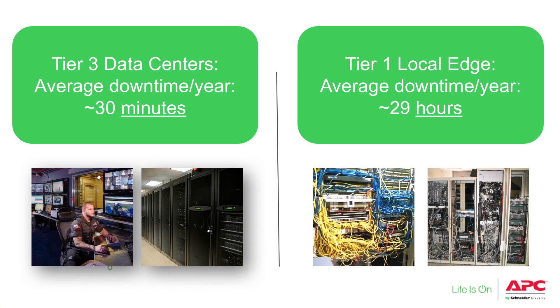And what that ultimately leads to is significantly less availability and more downtime. The average Tier 3 data center experiences roughly 30 minutes of downtime a year, where the typical local edge site experiences about 29 hours annually. And that's actually multiplied many times over, because with a typical Tier 3 data center a corporation might have one, two, maybe three — however, local edge sites could have dozens, hundreds, or thousands. So that downtime difference really understates the actual effect of having a lower-availability local edge deployment.